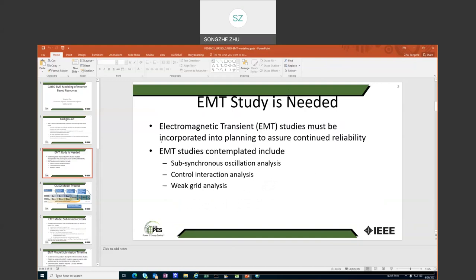So for California ISO, EMT study becomes more and more important. We must incorporate EMT studies into planning to ensure continued reliability. We are contemplating EMT studies focusing on subsynchronous oscillation, that is, the SSCI between inverter-based resources and series compensated transmission, the series effects on the transmission lines. We're also looking at control interaction among different IBR plants. And as more IBR replaces the synchronous generators, we anticipate our grid will become weaker and weaker, so weak grid analysis will be very critical for us.